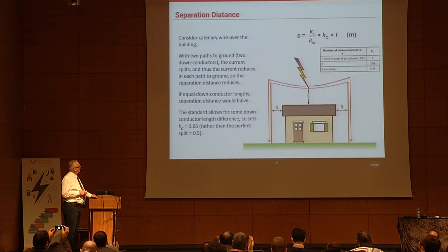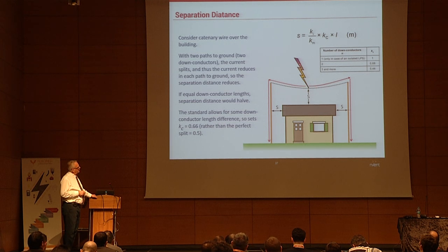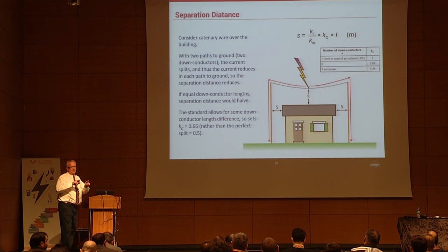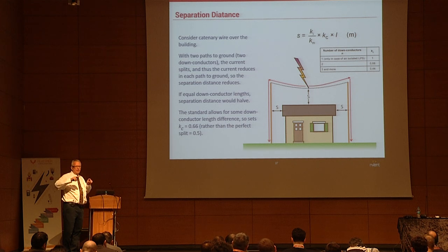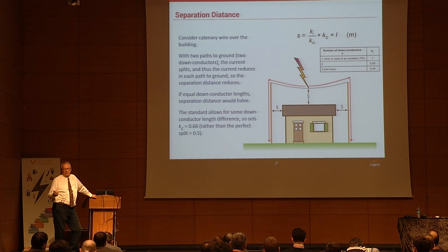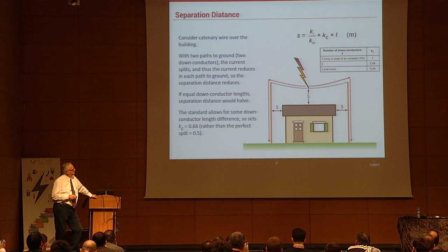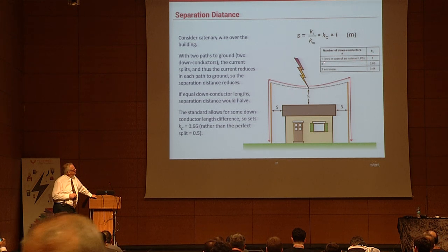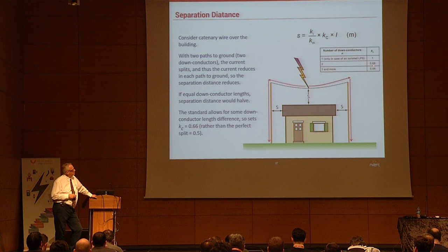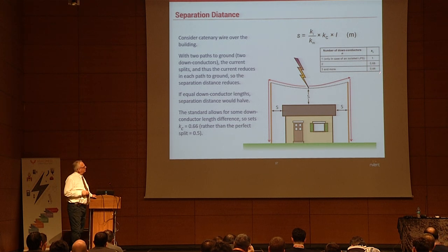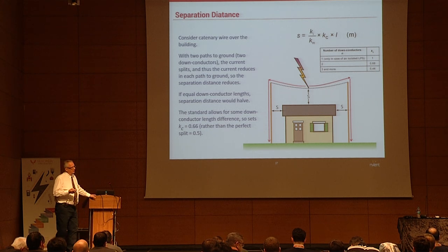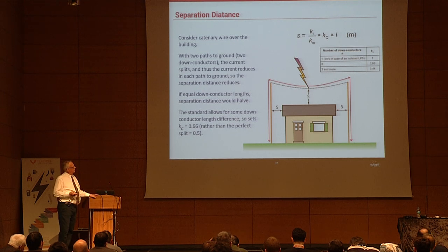In a more specific example with a freestanding mast and catenary wire, if the strike hits in the middle you'd assume current splits 50/50, but conditions aren't perfect — strike location and impedance variations affect the split. The Kc factor is 1 for a single conductor; for two conductors the standard says it doesn't split 50/50 but uses a factor of 0.66, and for three or more conductors it's 0.44. These constants include a fudge factor that helps with the calculation.